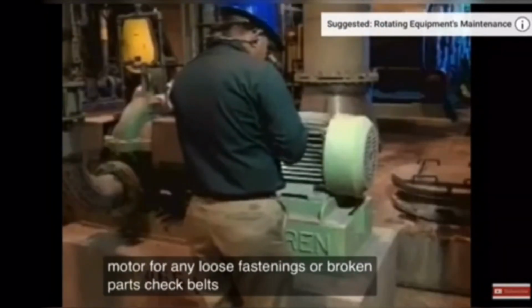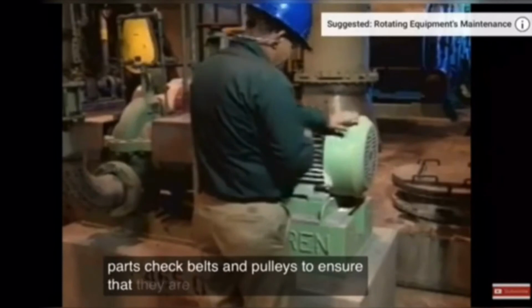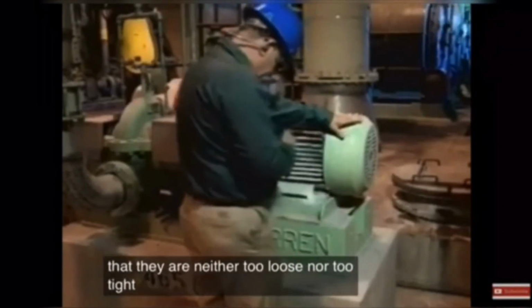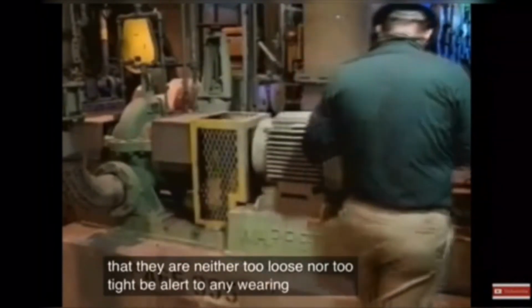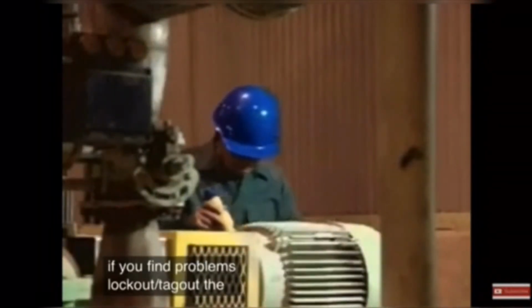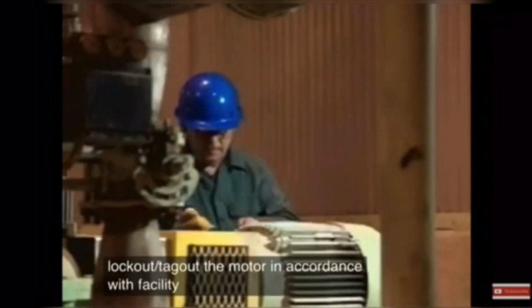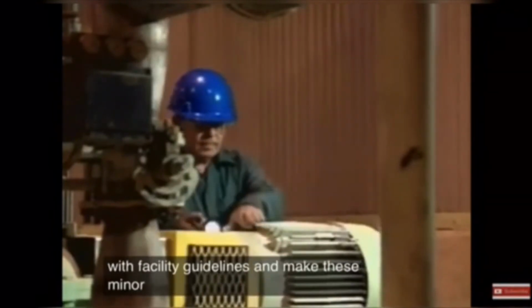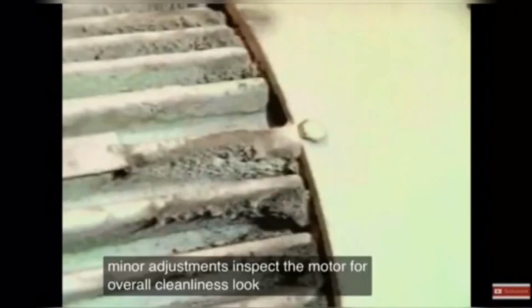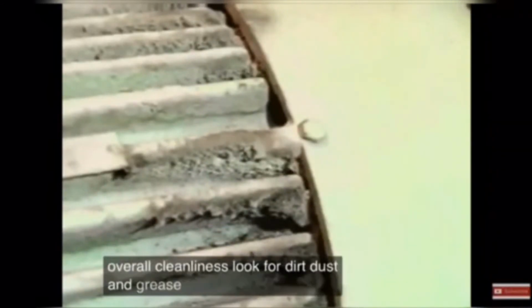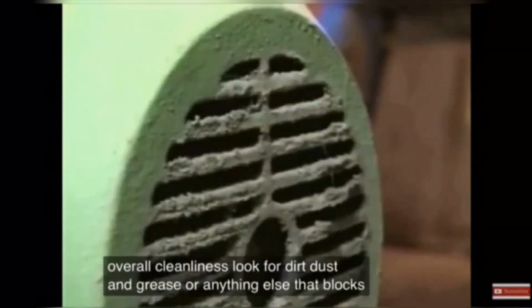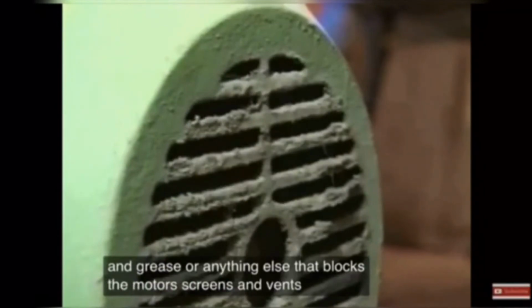Check belts and pulleys to ensure that they are neither too loose nor too tight. Be alert to any wearing or fraying. If you find problems, tag out the motor in accordance with facility guidelines and make these minor adjustments. Inspect the motor for overall cleanliness. Look for dirt, dust, and grease, or anything else that blocks the motor's screens and vents.